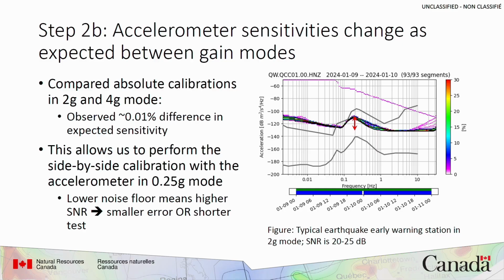So to make sure that this is okay, we actually did some checks, did some calibrations of the accelerometer using different full-scale modes, and found that they agreed to within 0.01%. So we're confident that you can change the gain setting on the accelerometer in the middle of a test, or between tests, between step 1 and step 2. I'm going to quickly get through this. The electrical calibration, I'm glossing over it a little bit, but I will note that there's a slight difference in the response of an accelerometer between DC and 0.2 hertz, which needs to be accounted for.